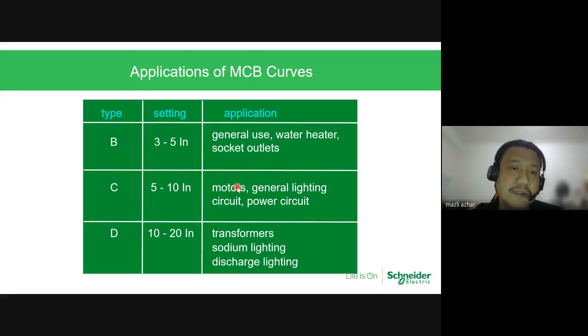If you are using a different type of MCB curve, but you are using the required rated current, then you may need to consider the type of unit to be used, B, C, or D, to ensure that you also cater for the starting current of the motor itself. So B is normally used for 3 to 5 times rated current, for general use: water heater, sockets, outlets. C, 5 to 10 times: motors, lighting circuit, power circuit. D is more for transformer, sodium lightings. Okay, some motors will require D. So this is very important for you to design and to ensure that you don't under design the breaker for the type of load you are supplying.